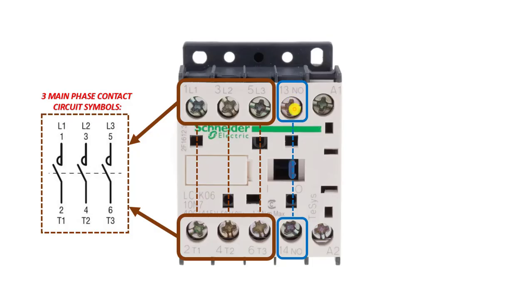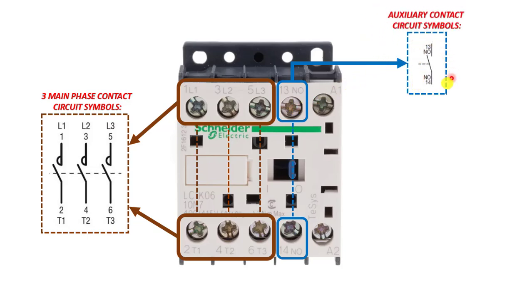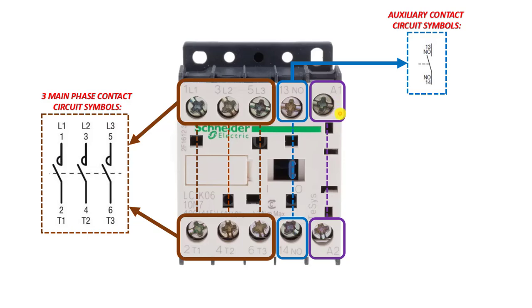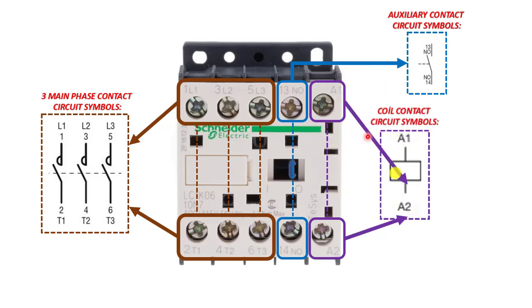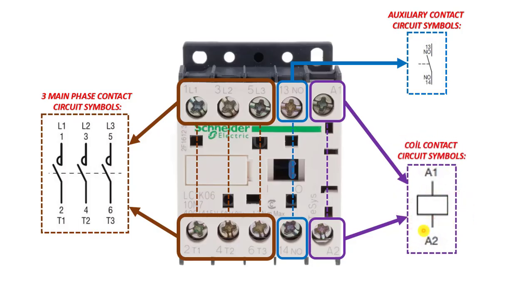With this auxiliary contact we can control any extra load. The circuit symbol represents a single open contact. The input leg of the auxiliary contact is numbered 13 and the output leg is called 14. Then we have the coil part of the contactor, to which we connect our control circuit. There are A1 and A2 contacts — this is the signal required for remote control. We apply the required voltage to these coils.